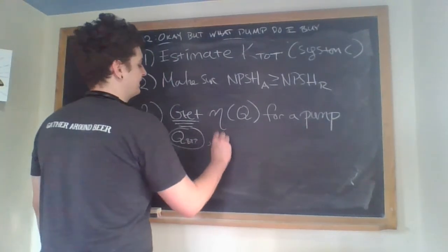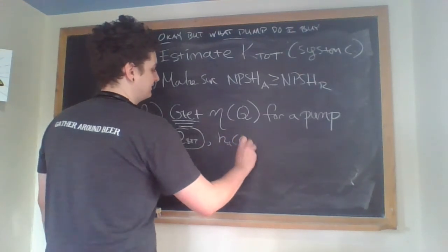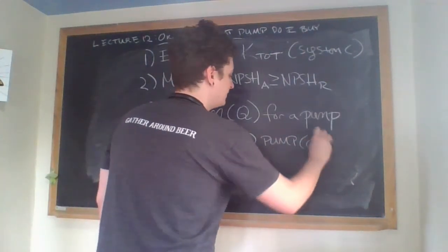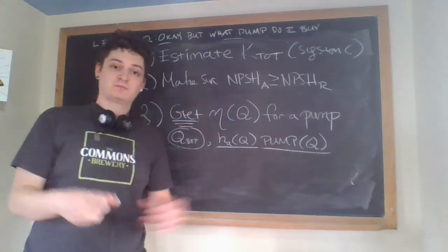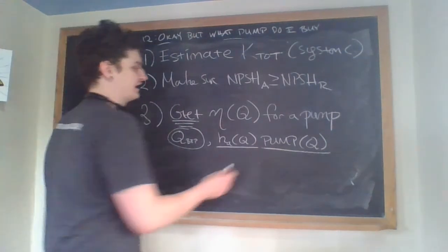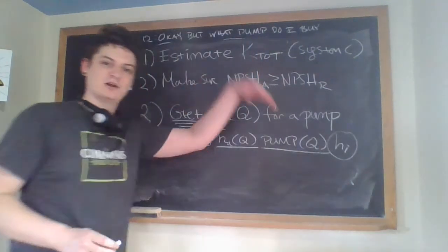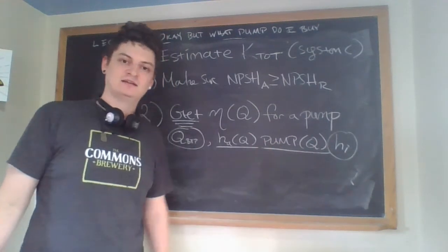What else do we have? So you have this plots the system curve. This gives you the Q_BEP, and it actually gets you this pump curve, this step. So this step right here is obtaining this pump Q curve, because you're selecting a pump that has a pump performance. If you were designing the pump, you would start with the ideal case. If you're designing a pump, you just have this H_I. That's the lecture we did before. That was a linear, totally wrong approximation. But it can get you on the right track on this selection idea.